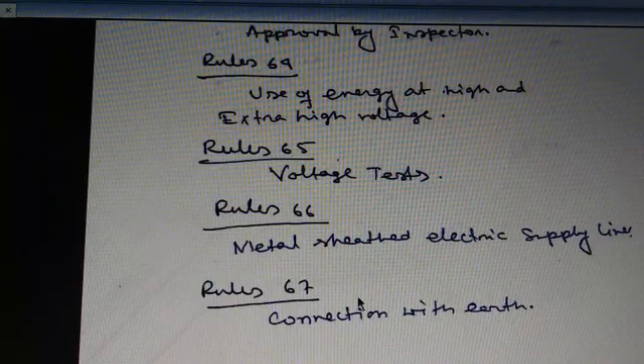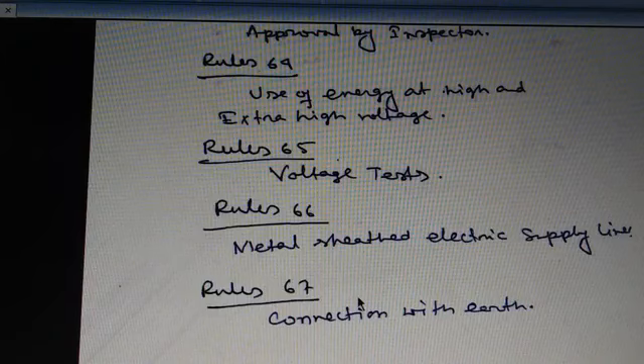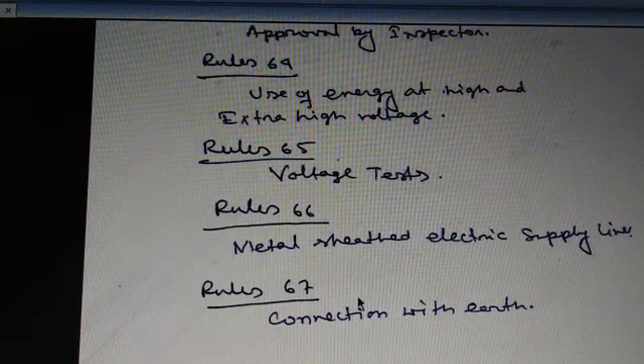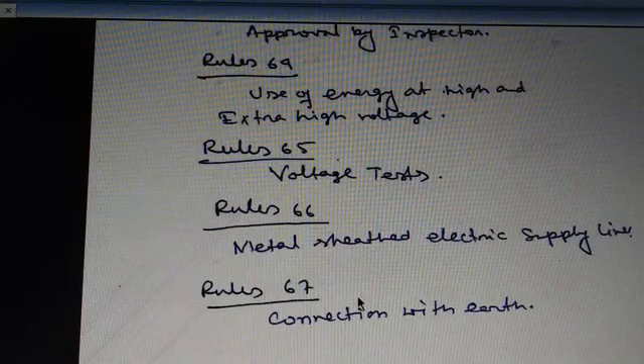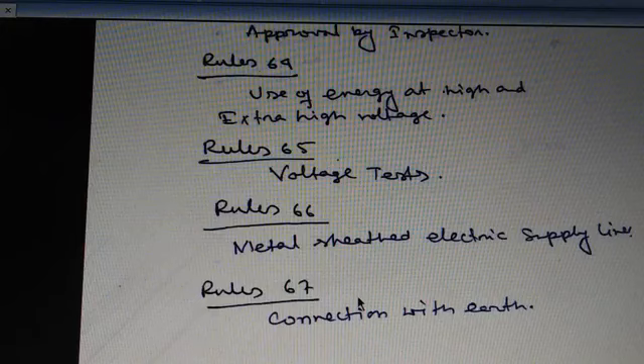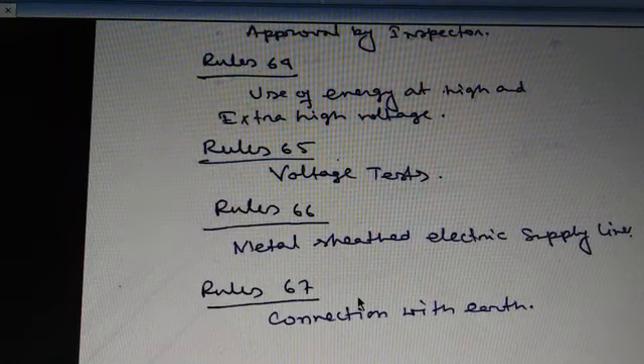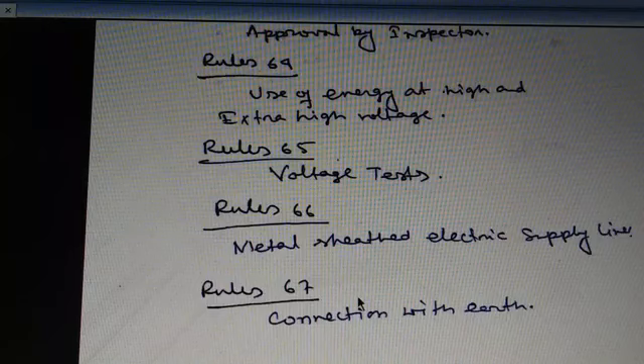Next, in the event of appreciable harmonic currents flowing in the neutral connection, so as to cause interference with communication circuits, the generator or transformer neutral shall be earthed through a suitable impedance. Next point, single phase high and extra high voltage system shall be earthed in a manner approved by the inspector. Next point, in the case of a system comprising electrical supply lines having concentric cables, the external conductor shall be the one connected with the earth.